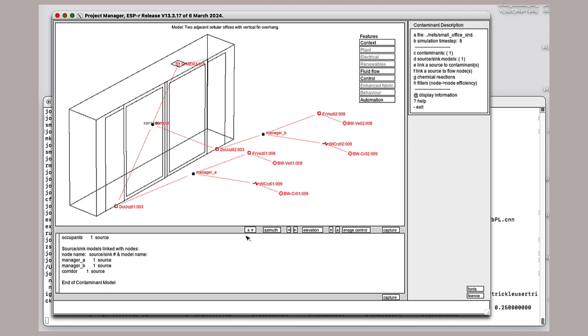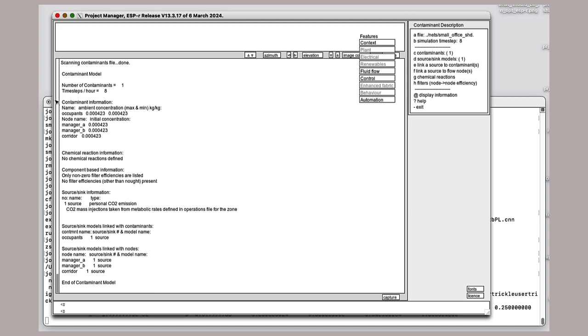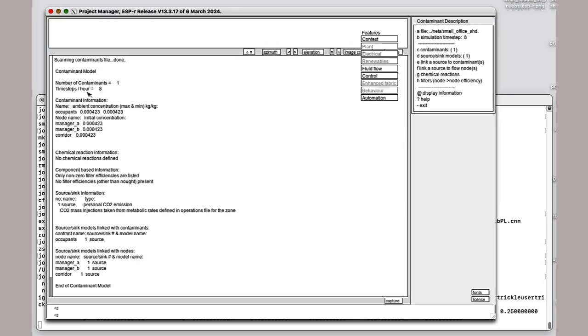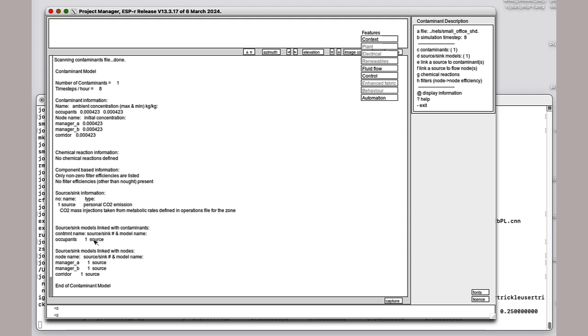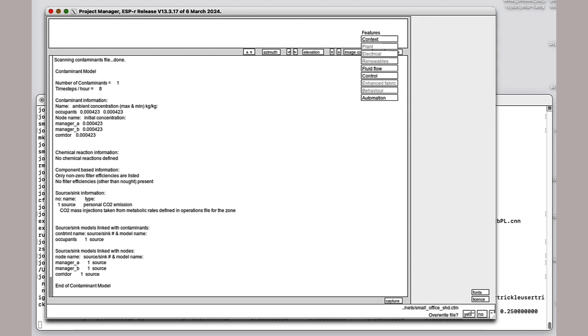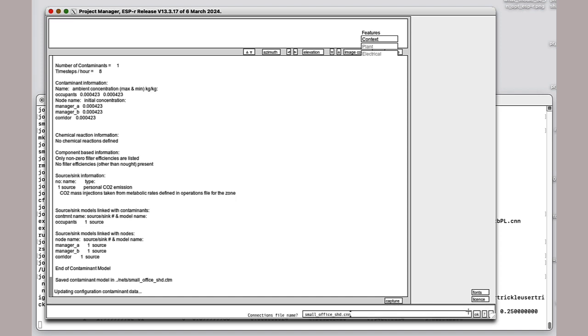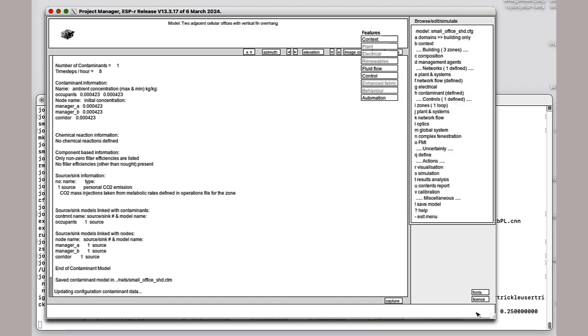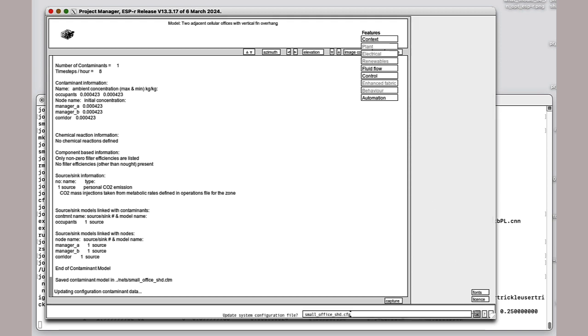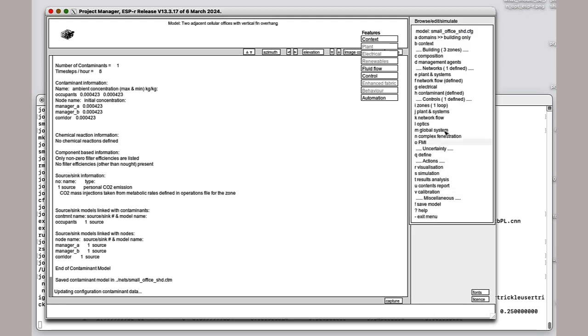The synopsis, basically, I've got one contaminant. It has an ambient concentration, and that's been associated with each of the nodes as a starting point. I've got no chemical reactions defined. I have a source based on personal CO2 emissions, and I have a type I'm creating called occupants. Then each of the zone nodes in the flow network are associated with that type of source. That's my contaminant model. If you were going to change some things, you might go in and look at any of these particular zones and say yes, overwrite that and update that we do actually want contaminants included in our model.